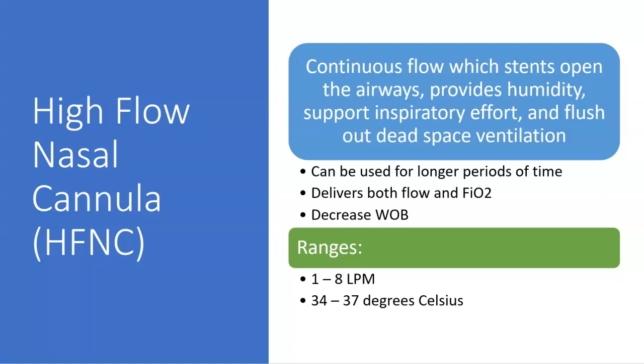beneficial in our lungs. It can be used for longer periods of time on lower settings with a swallow eval and physician consideration. If typically 2 to 3 liters, a baby can actually feed on high flow, which is a game changer. We deliver both FiO2 and flow, and then our goal is to decrease work of breathing. For neonates, we want to go between 1 and 8 liters per minute, with the set degrees at 34 to 37 degrees centigrade.